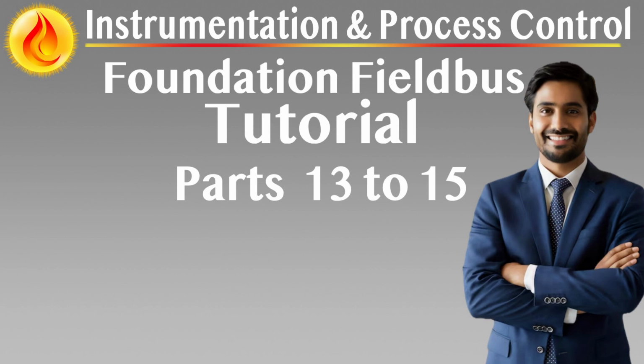Finally, the planning phase must result in a comprehensive engineering deliverable set, including segment drawings, device lists, function block schedules, I/O allocations, power budgets, voltage drop calculations, network load analysis, and configuration databases. These documents form the blueprint for the next project phases: design, installation, commissioning, and operation, and are critical for risk reduction, procurement alignment, and schedule control.